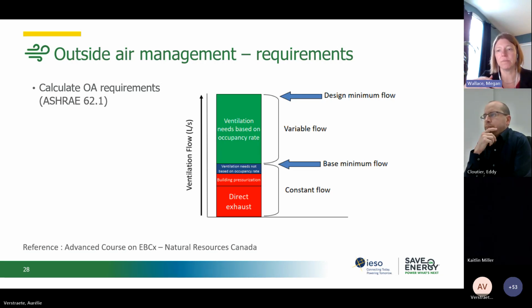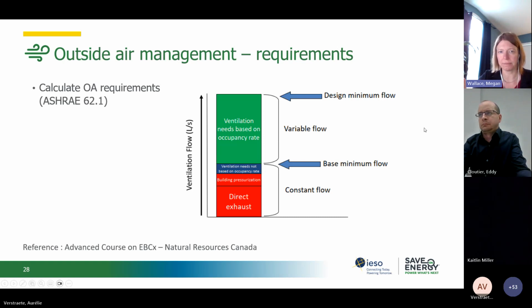Ventilation needs not based on occupancy, so minimum outdoor air per square foot of the building. Then there'll be a portion of the outdoor air required that is based on your occupancy rate. ASHRAE 62 says you need so many CFM, or cubic feet per minute, of outdoor air per person. That's a variable amount based on how many occupants you have in the building.